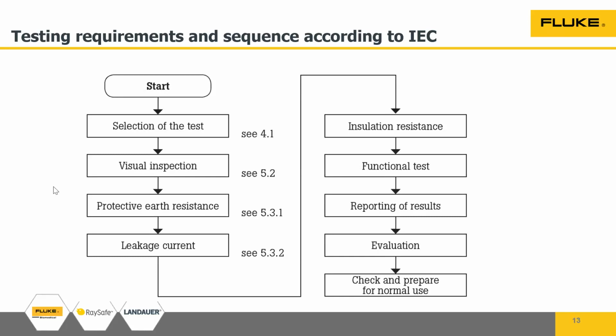Electrical safety is paramount and most important, and it is the most common thing that has to be done across any medical device, whether it is a basic ECG machine, a defibrillator, or a heart-lung machine. Anything and everything, electrical safety is paramount and basic. And then next is parameter testing. Particular machines will have other measurement parameters, like a ventilator will have flow, pressure and breath parameters. Based on that, you have to do those kinds of parameter testing, which is like functional testing of the device.